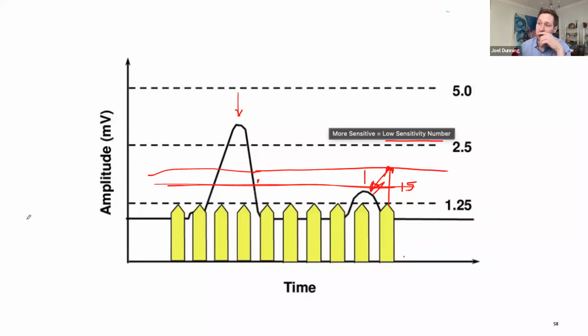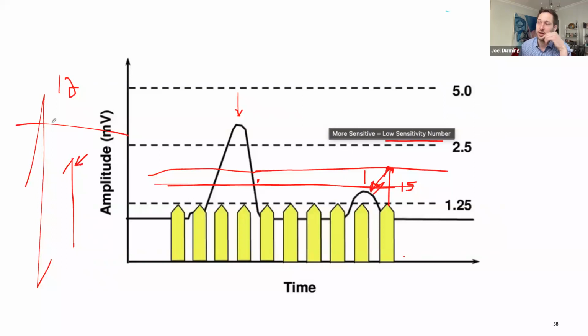Things to keep in mind though, PVCs tend to be wide and ugly. They tend to be very tall. So if you measure a PVC, it could be 12 millivolts, but their intrinsic could only be 6 millivolts. So you don't want to program based on PVCs because you'll set your sensitivity setting so high that you never actually see the intrinsic conduction. So just things to look for there. Does that make sense?